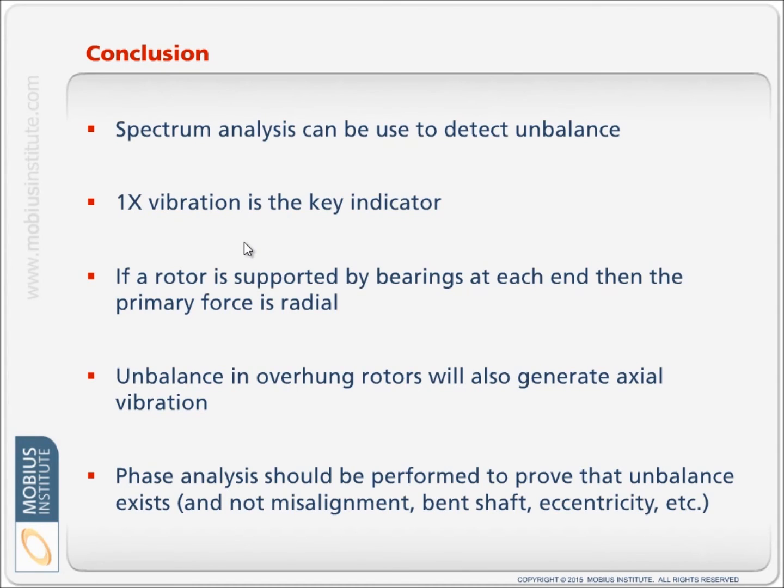But there are a lot of fault conditions that will provide a 1x peak. So even though you may be looking at a fan and you say it's most likely to be unbalanced as against eccentricity or bent shaft or some other sort of fault that generates 1x vibration.